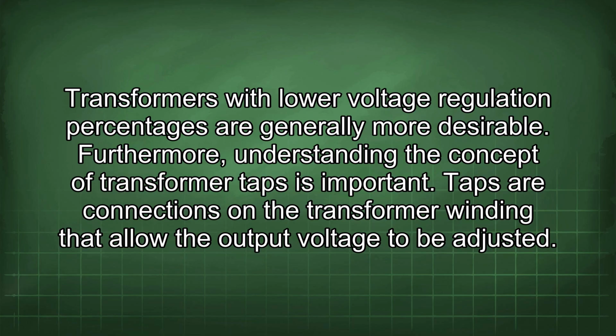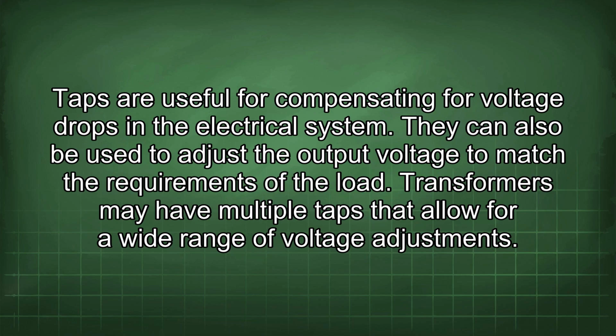Furthermore, understanding the concept of transformer taps is important. Taps are connections on the transformer winding that allow the output voltage to be adjusted. Taps are useful for compensating for voltage drops in the electrical system. They can also be used to adjust the output voltage to match the requirements of the load. Transformers may have multiple taps that allow for a wide range of voltage adjustments.